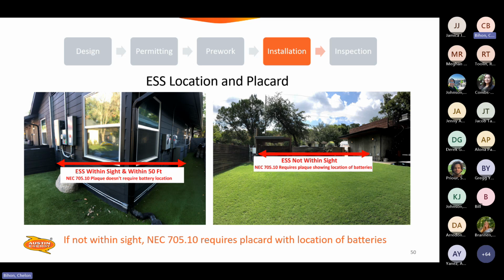ESS location and placard. ESS on the left picture within sight and within 50 feet doesn't require a placard. It's on the corner. You can stand back and you can see everything. When the ESS is not in sight, it could be behind a gate. There could have been a gate on that corner, and then it would have required a placard. It doesn't take much to put it out of your sight. We do require a placard if it's not within sight.